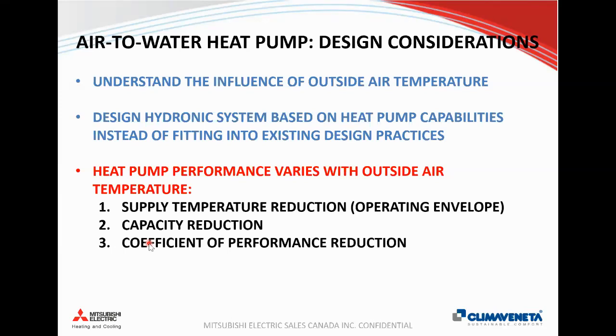And because we have a refrigeration cycle, as it gets colder, it's harder for the machine to extract heat. So our capacity will decrease. So we need to understand how that's going to reduce as it gets colder outside, and perhaps we can strategically select the sizing of the unit based off of supply temperature that we want to get as much BTUs out of the machine as we can. So along with the capacity reduction, we also have a coefficient of performance that will reduce, but again, the minimum COP of these machines, and we'll have examples coming up, is always above 2.